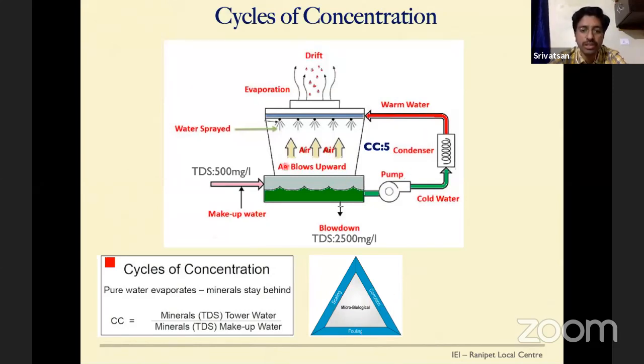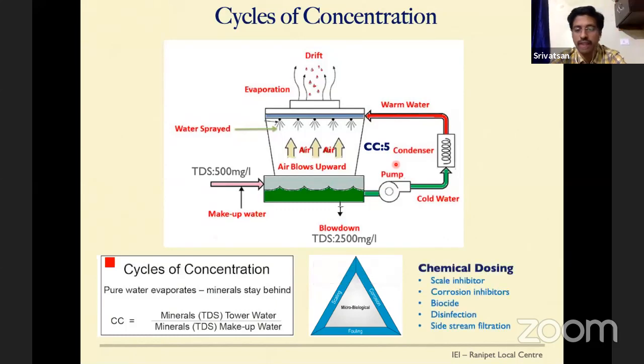What I'm talking about is the cooling water basin, the tower, the sprinklers, everywhere. So we need to keep this water in condition so that it doesn't have an adverse effect on the condenser tubes or all the piping and equipment. So what is the remedy? We have to do some chemical dosing continuously to maintain the quality of water in the cooling water cycle.